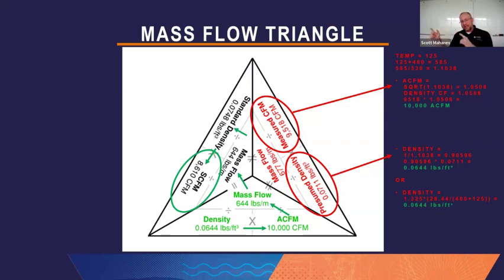I'm moving 8610 CFM at the fan inlet. In fact, if I were to measure this duct traverse at standard density conditions, which I think is below 70 degrees, but if I was reading this at a lower temperature, I'm going to see that I'm actually moving closer to the 8610 CFM. The problem is the allocation of where I measure the flow rate. I can't measure 10,000 CFM at a different density and allocate that measurement to what the fan's moving. That's not going to be right.